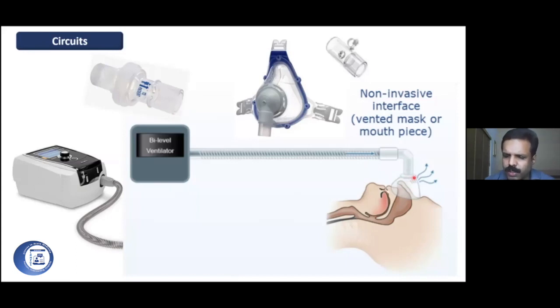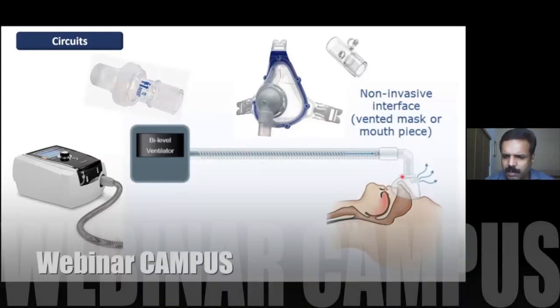Okay, so in other words, you need a leak port in the face mask. Otherwise, there will be carbon dioxide retention and again barotrauma. So once again, whenever you use a single limb circuit, the mask should have a leak port. So this can be done in different ways.